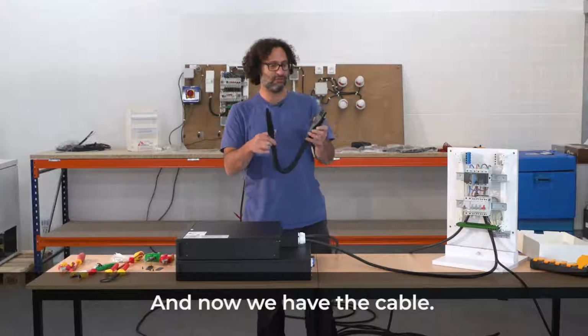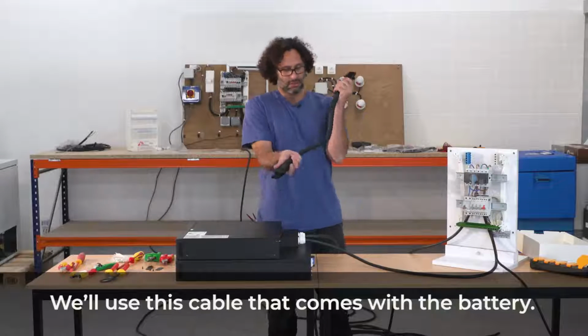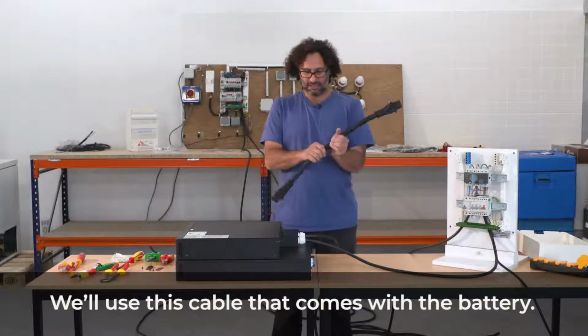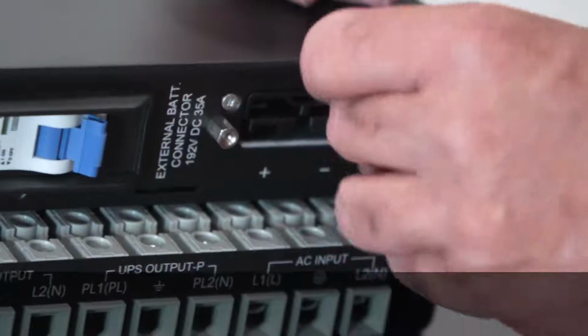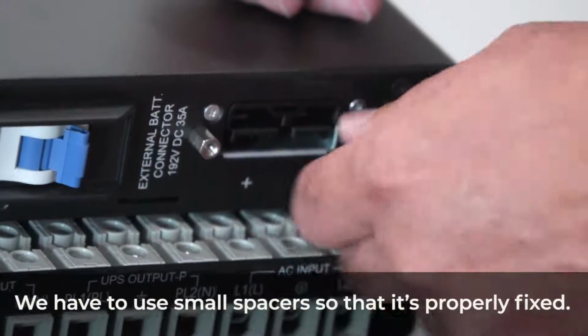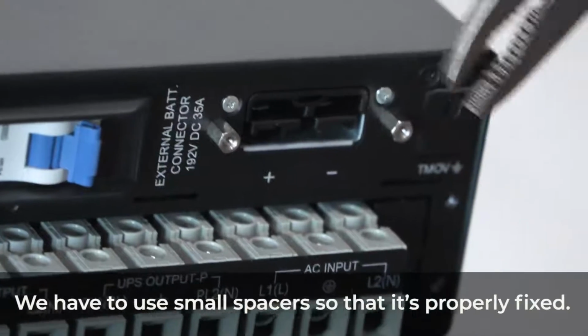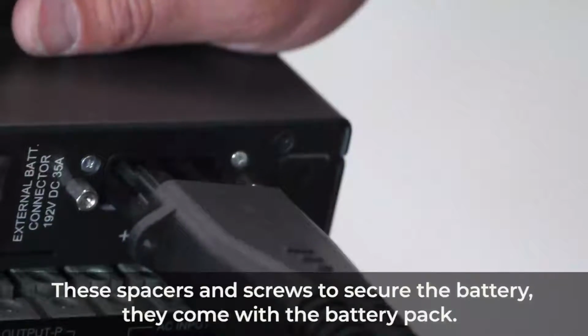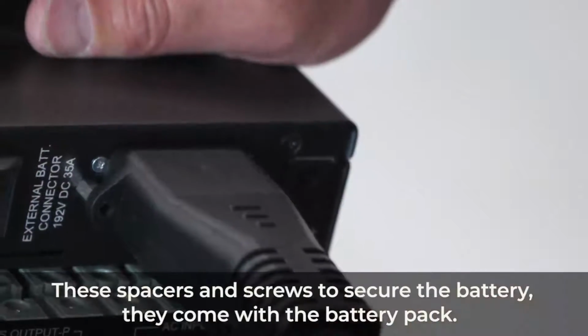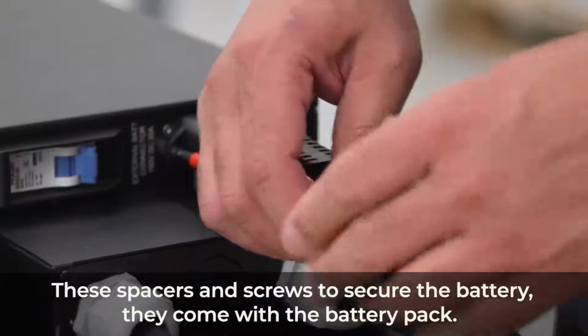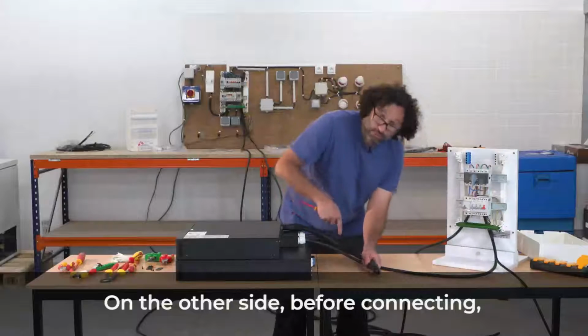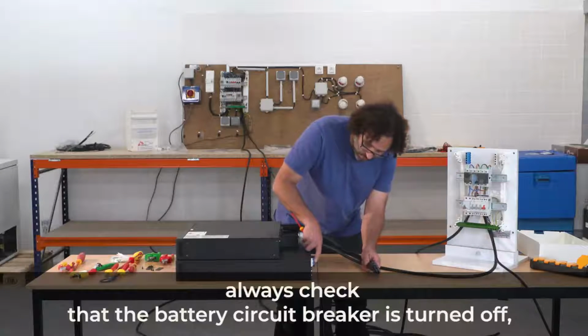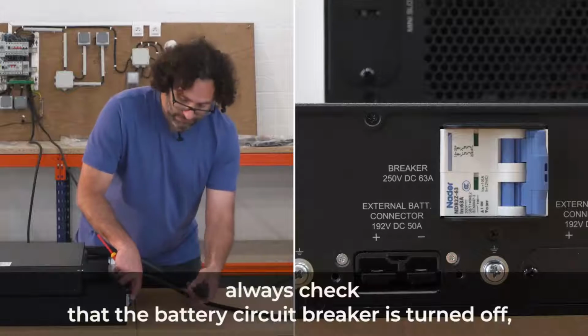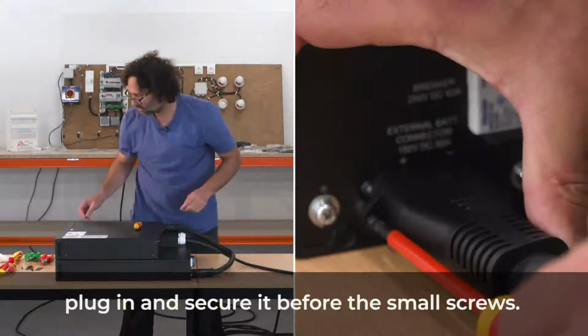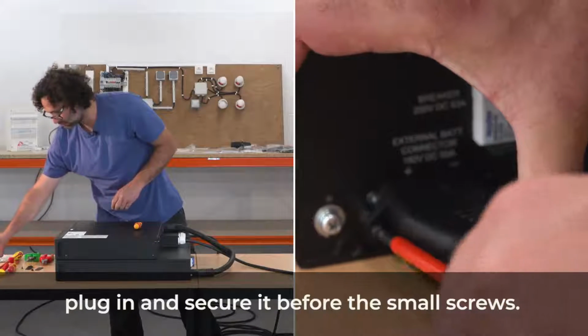And now we have the cable. We'll use this cable that comes with the battery. We have to use small spacers so that it's properly fixed. These spacers and screws to secure the battery, they come with the battery pack. On the other side, before connecting, always check that the battery circuit breaker is turned off, plug in and secure it before the small screws.